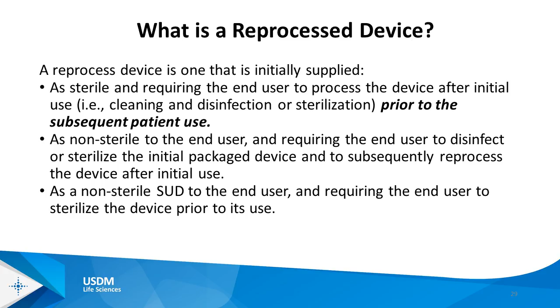So there are some devices for which the label can also act as a direct mark. So you need to understand the difference between these and how they overlap. More importantly, you need to understand what is a reprocessed device. So not everything that is reused is necessarily a reprocessed device that is subject to the direct mark requirement of the regulation. This is all information taken out of existing FDA guidance documents, but I think the critical point about a reprocessed device is that it is reprocessed in order to be used on a subsequent patient. So hopefully everyone understands that I clean or I disinfect or I sterilize a device after one patient so that it can be available for use on a subsequent patient. That is the notion, if you will, even the definition of what is a reprocessed device. So if you have a device that fits into this category, then it's subject to direct marking, and you need to also apply the direct marking requirements of the rule.